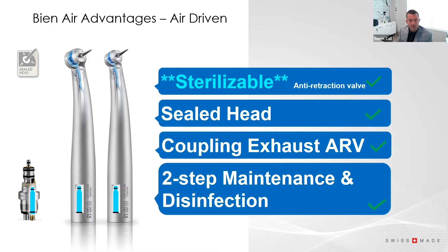Bien Air's second exclusive design is an anti-retraction valve in the exhaust of the coupling. So if you're using an air-driven handpiece by Bien Air, you actually have two anti-retraction valves. One prevents the retraction of the irrigation water that's used to create the spray. Then you also have protection in the form of a sealed head, so nothing can enter the head of the handpiece and be exhausted back down. And then you have a third barrier of protection, which is another anti-retraction valve in the coupling.